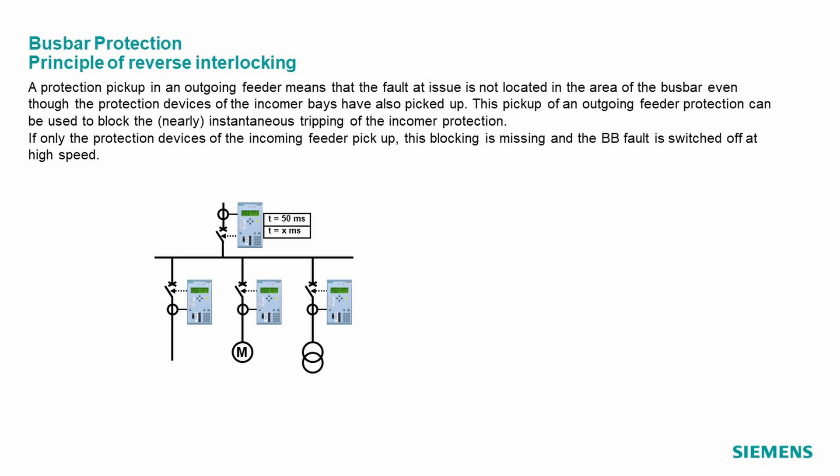The simplest busbar protection can be built according to the principle of reverse interlocking. The advantage of this principle is that the application can be implemented with the same protection devices that also protect the lines and cable routes. This means that no additional equipment is required.